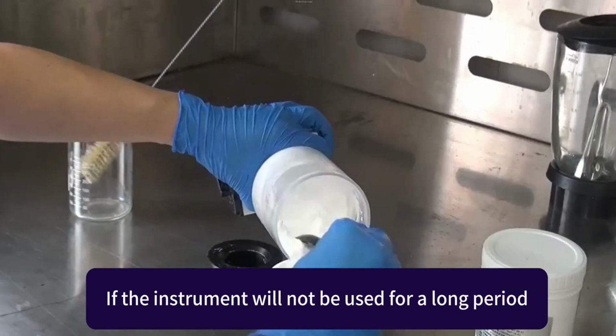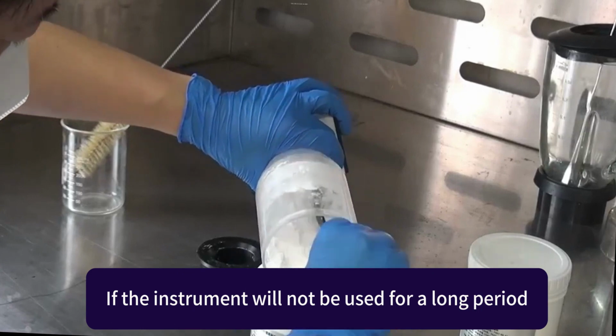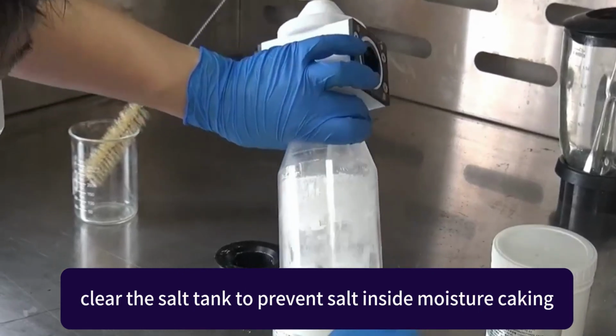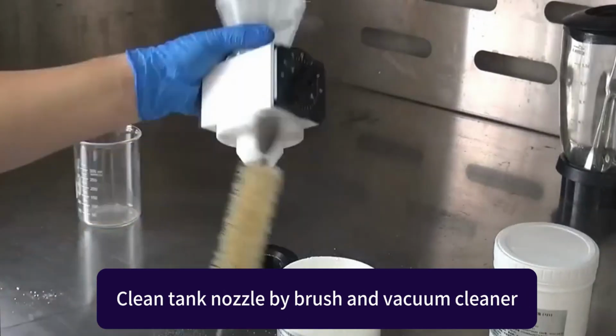If the instrument will not be used for a long period, clear the salt tank to prevent the salt inside from absorbing moisture and caking. Clean the tank nozzle with a brush and vacuum cleaner.